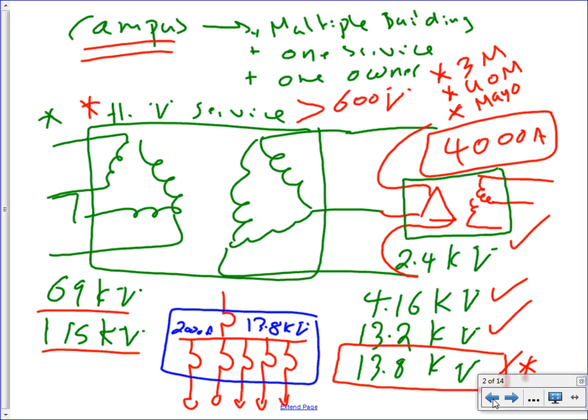Take this, for example, a 13.8 switchgear. These conductors right here are my service entrance conductors. So who installed the service entrance conductor? Us, even though they're 13.8, and they land in a 13.8 switchgear. Now, where does Excel start? I assume Excel is bringing the cable right here. Typically they have a pole here with the power lines, and they have a fuse disconnect right here, and they tie their cable in here, and from here it will be tied to their system.